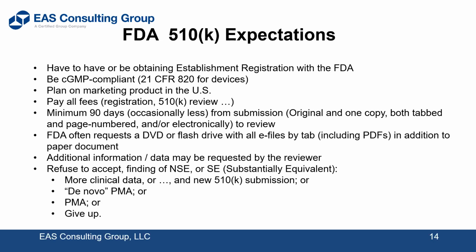In most cases, the FDA's GMP inspection is still tougher than a notified body inspection for the CE mark in Europe. And I base that on CAPA issues and, as I mentioned earlier, on risk. I've dealt with 2 companies recently, in Europe and Asia, that got warning letters from the FDA on this issue of risk, because they were taking a broader view of it, and the FDA has a narrow patient risk issue.